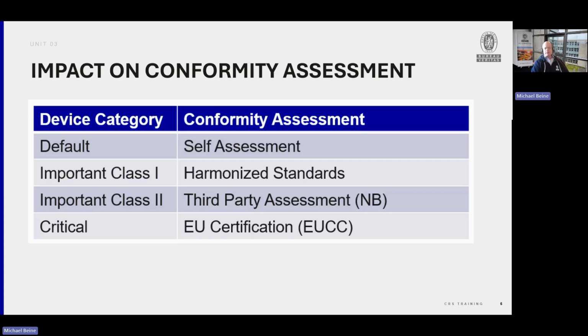It's a quite formal aspect. The manufacturer supplies all those documents and evidences, including test reports, and then the notified body looks formally at it, makes sure that it all fits together, follows all the rules, and then confirms the compliance to the regulation, where a test report confirms the compliance to the standard. So that is, I think, an important aspect to look into. All that needs to come together to get this notified body EU type examination certificate.